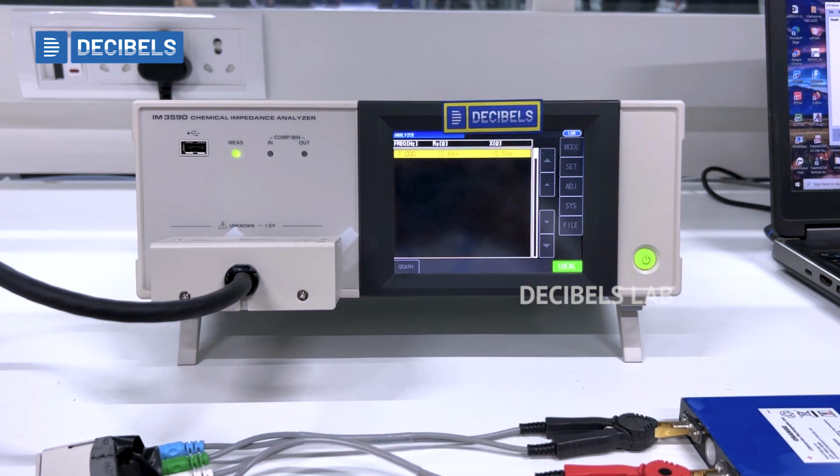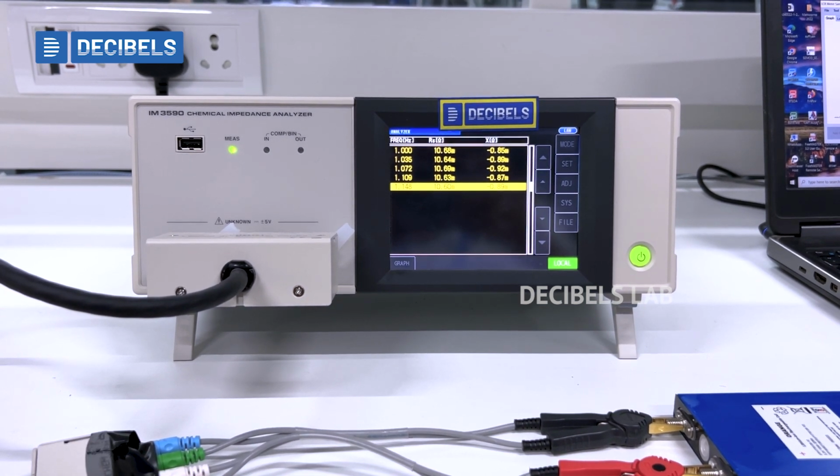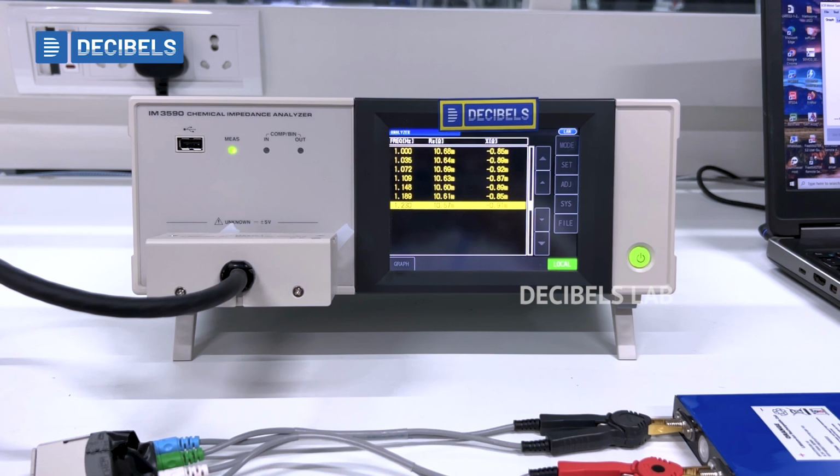So what do we do with the help of this equipment? It is very simple and straightforward to use the equipment and conduct a test. But what is more important for you is to get the data and make meaningful sense of the data that is coming out of this machine. Here we have from Hioki the IM3590 chemical impedance analyzer. This can do 1 millihertz up to about 200 kilohertz of frequency range. For now, we are testing an LFP prismatic cell.